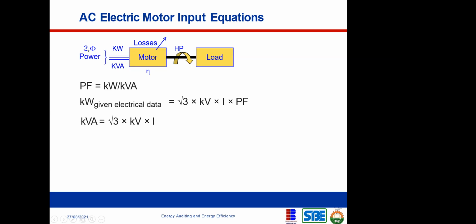So here you can see that this is three-phase power. It could be either kilowatt or kVA. This is an apparent power coming into this motor. Then, of course, the motor transforms this electrical energy into mechanical energy and it comes out in horsepower. Then you're using the rotational speed to power your load. That is the whole essence of having a motor. And we know power factor. Power factor is equal to kW over kVA, period. Now we know the input power to this motor.